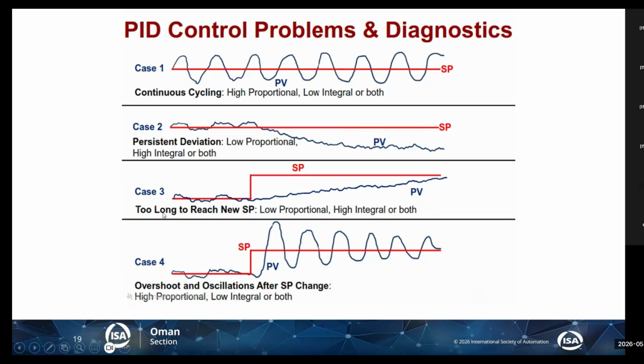Okay, I have case 3. You can see it takes too long to reach the new set point. It is very slow. It is reaching the set point, though it is taking more time. And you cannot accept this in the industry. That means you're losing something. So this can be because of low proportional and high integral, or both.